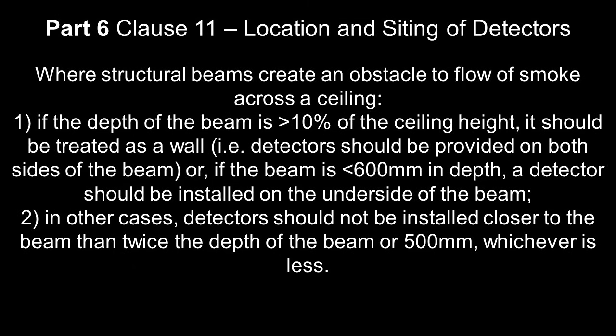Okay, but if the beam is less than 600mm in depth, a detector should be installed on the underside of the beam, because obviously we can install detectors from ceiling height all the way down to 600mm. So if the underside of the beam is 600mm, then we can actually install a detector on the underside of the beam, which means that you don't need two detectors either side. In other cases, detectors should not be installed closer to the beam than twice the depth of the beam, or 500mm, whichever is less. I hope that makes sense.